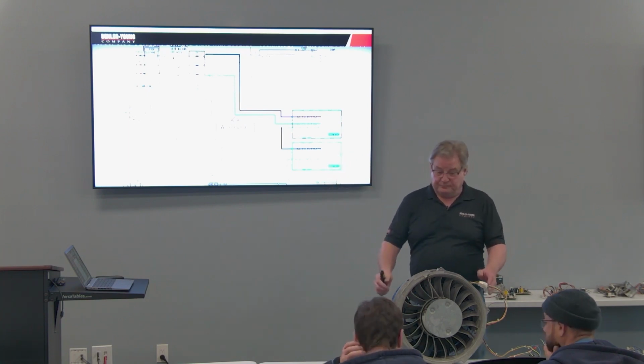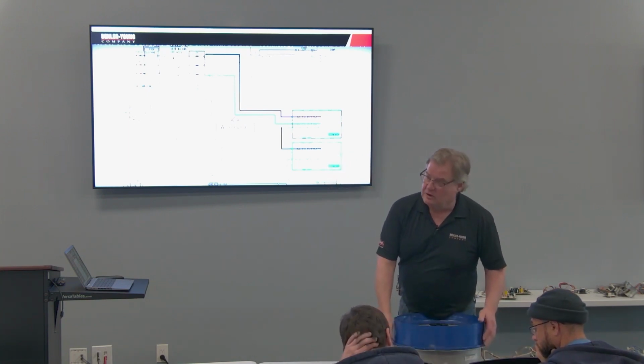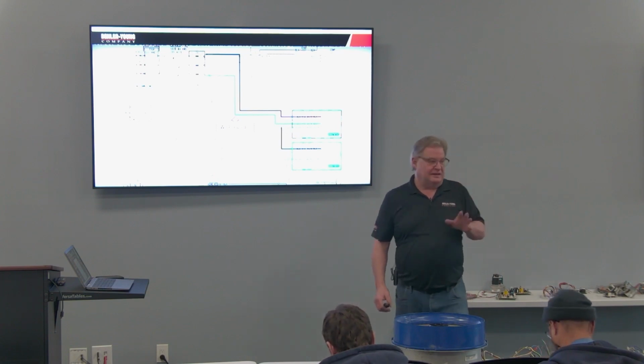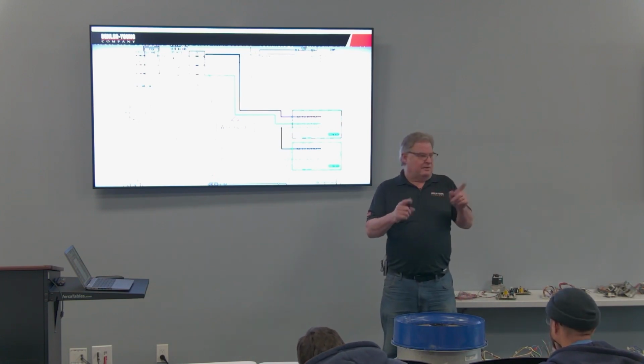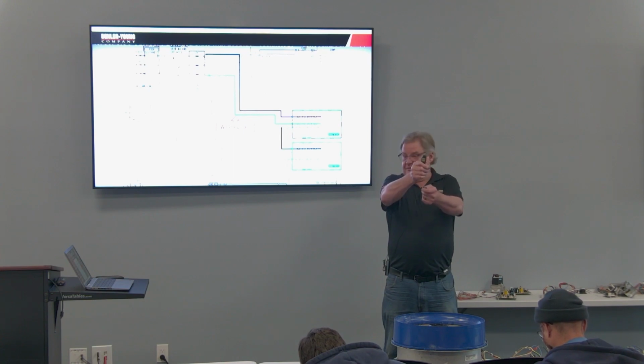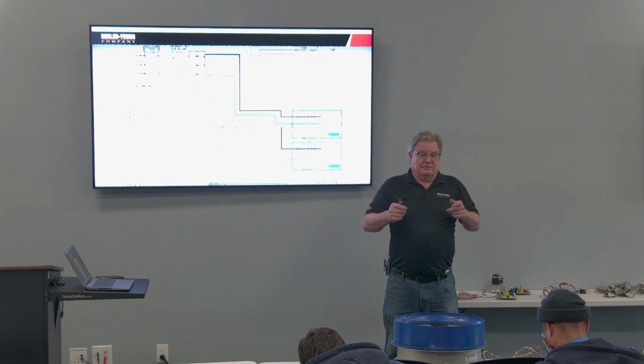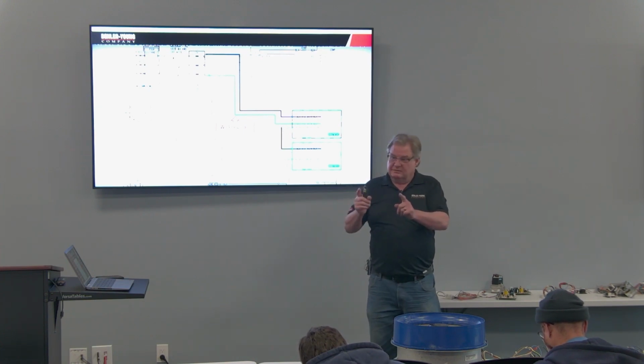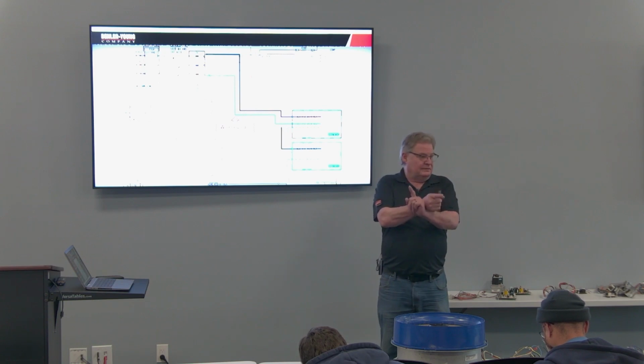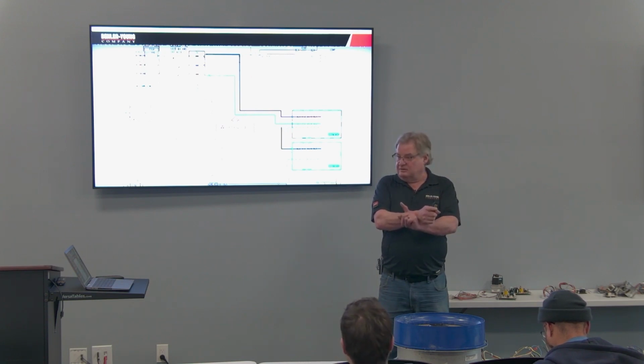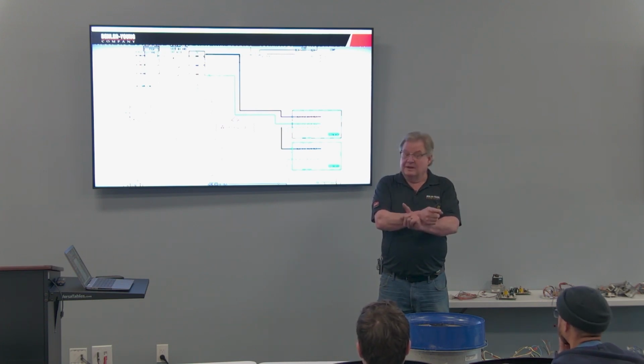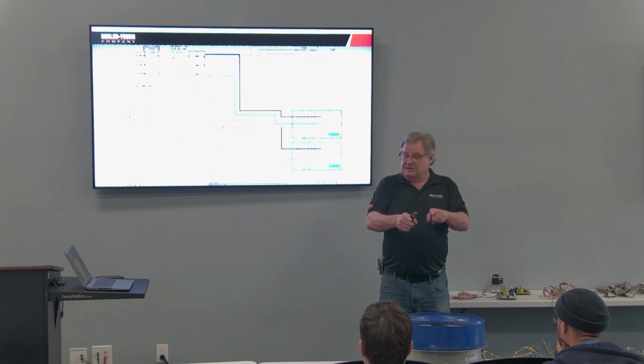Now, I'll warn you though, and think about this for a second. If I go up on a unit that's been around for 2 years, but I've bought 3 blower motors, geez, I've got a wild leg on L2. Well, I'll just go to my disconnect and move it to L3, right? Everything's good. What did you just do though to your compressors? I just reversed the compressors. That motor is going to spin the right direction no matter what.